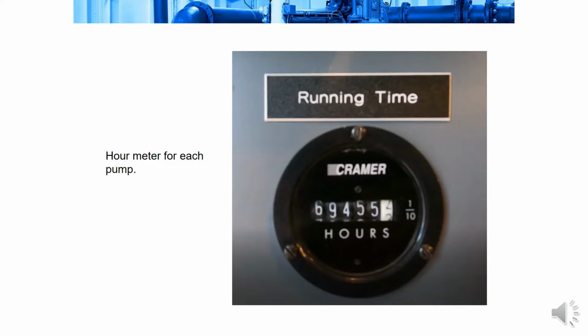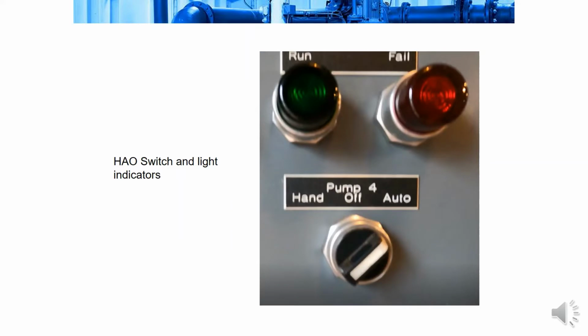Each pump has its own hour meter, which is important to use for maintenance and ensuring that pumps are being equally balanced. The hand-off auto switch and light indicators are part of the PLC control systems, showing if the pump is running under control or if it's running in hand mode, where it will just be running continuously.